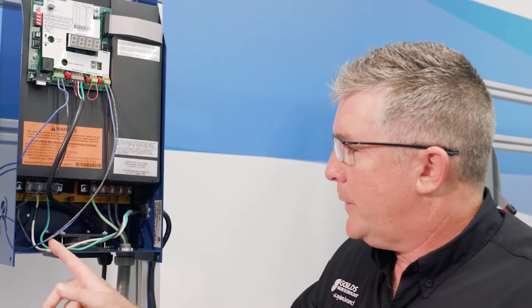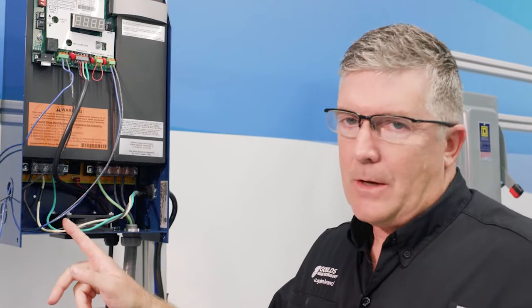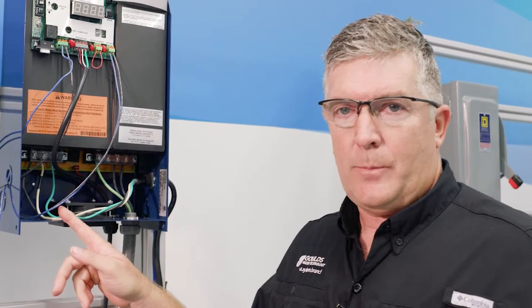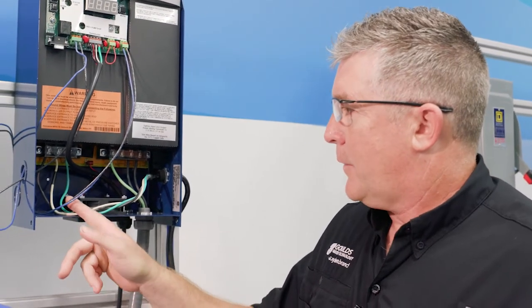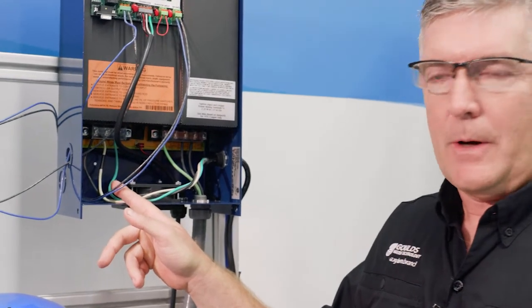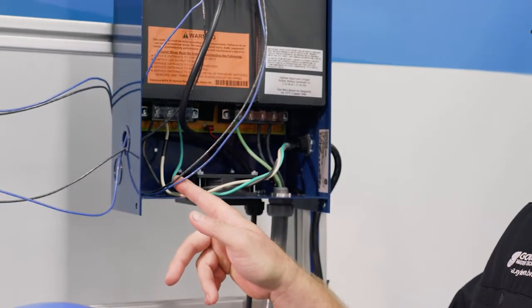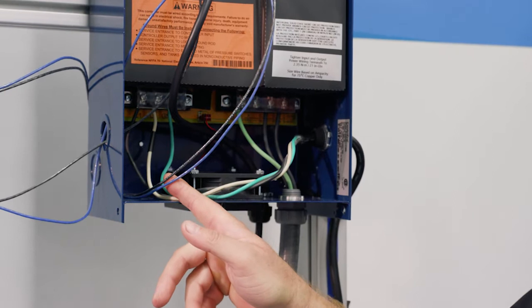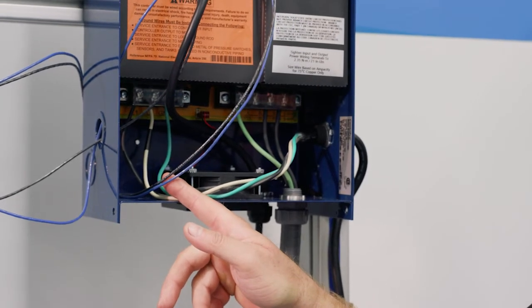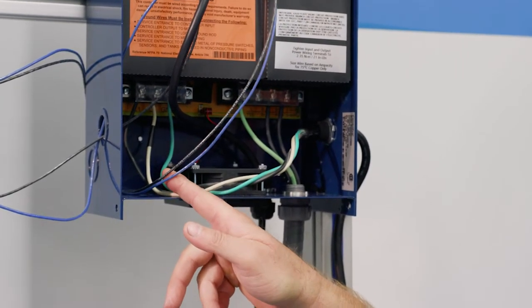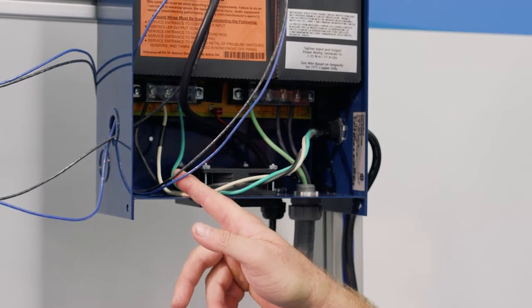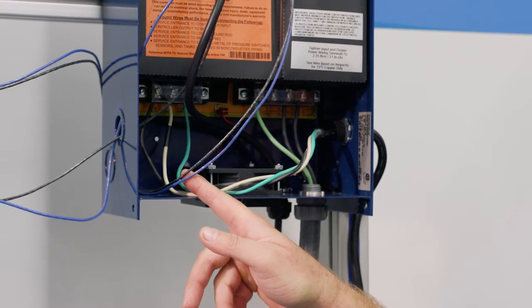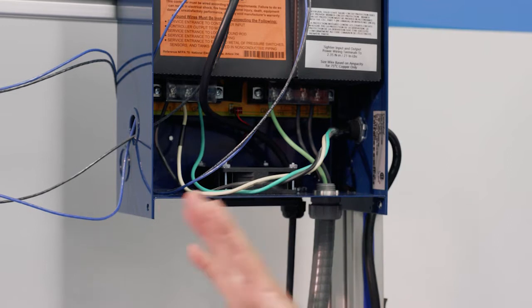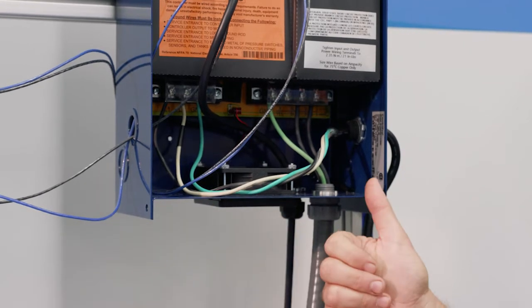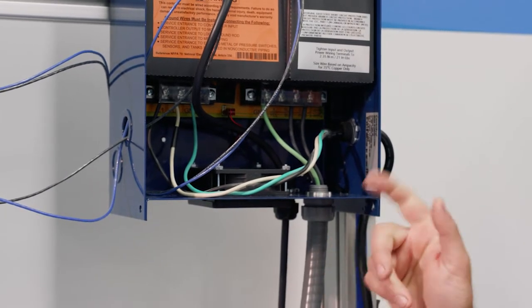So I'll do a quick overview of the input. These are 230 volt supply input. We do have a little black piece of tape on the white wire, just as a reminder indicating that we do have 230 volts coming in. So 230 volt is required for this drive, so that's on the input. Typically, input is on the left-hand side, and our output is here on the right, so that's power to the motor.